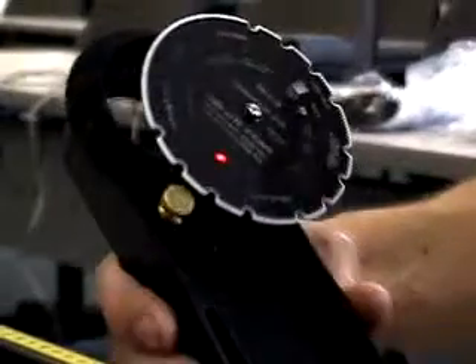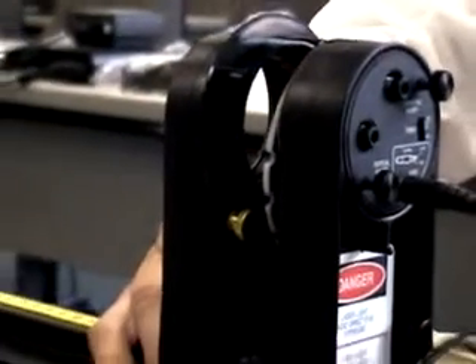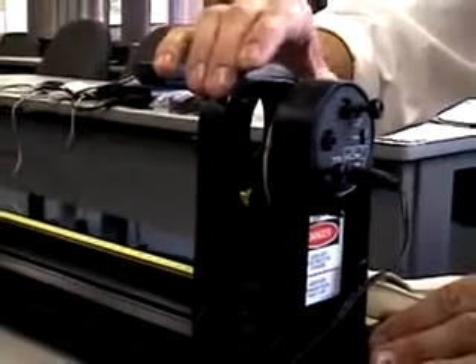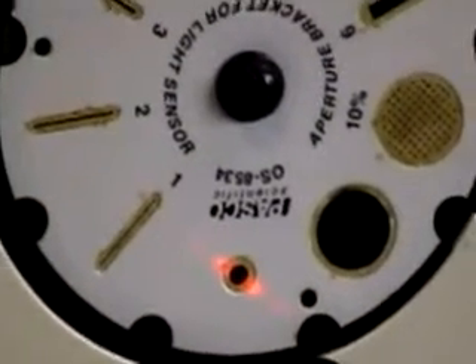Right about there. And using one of the slit accessory dials, you mount this in front of the laser so that when you change the dial, you get different patterns and then different slit widths. So now you can see that the laser is aimed into the barrel of the light sensor, but the diffraction pattern is off at an angle, and we'd like it to be level. So then we need to do a little more adjustment on the slit accessory. This screw here allows us to loosen the dial so that we can rotate it, so that the diffraction pattern will be level with the linear translator. So now we can see that we have a diffraction pattern that's relatively level there.